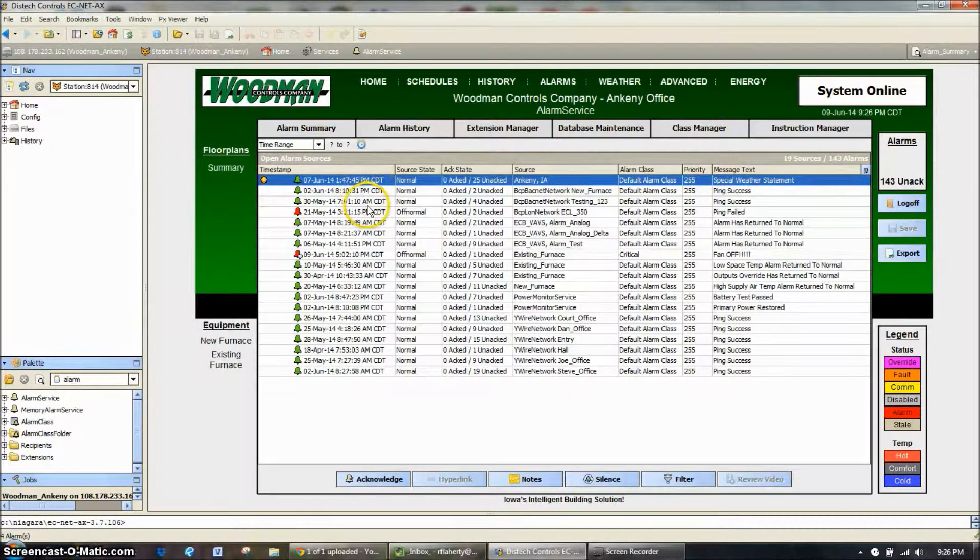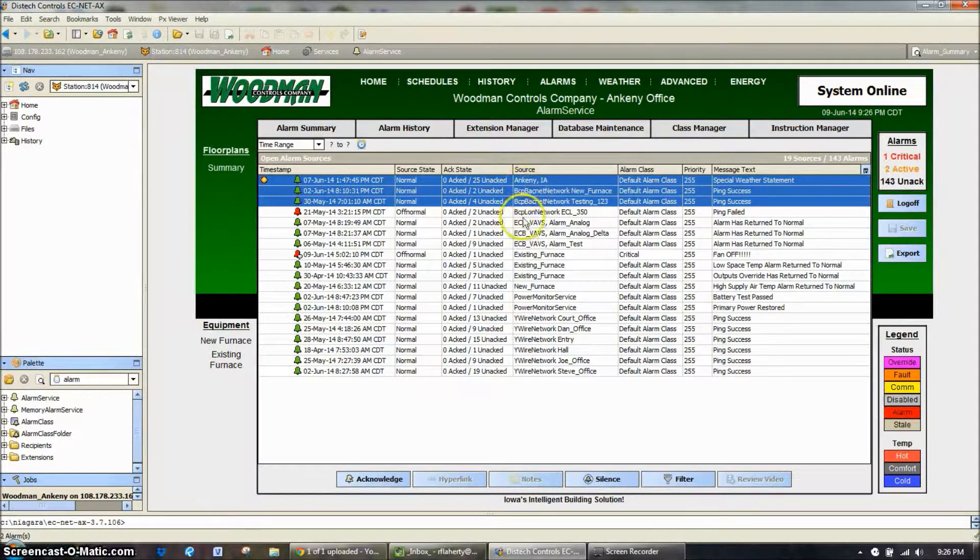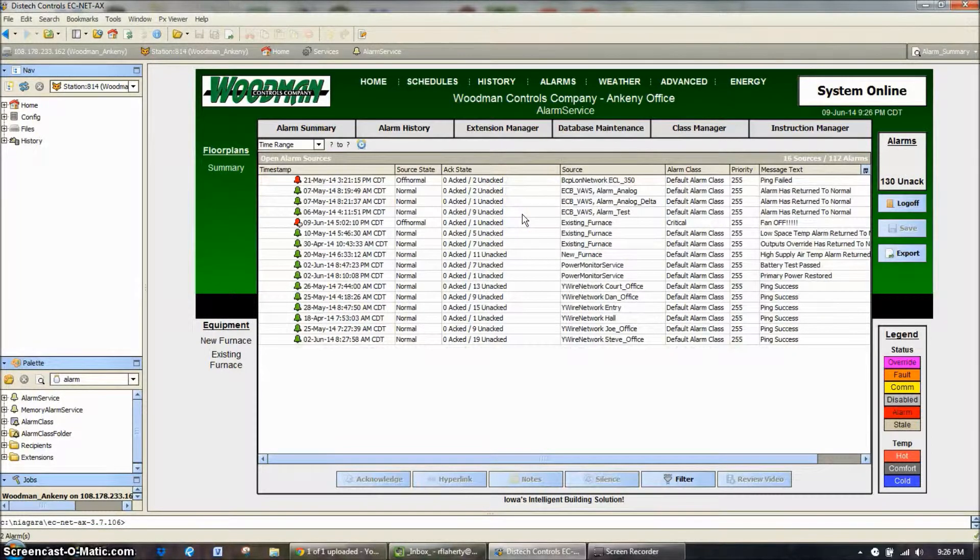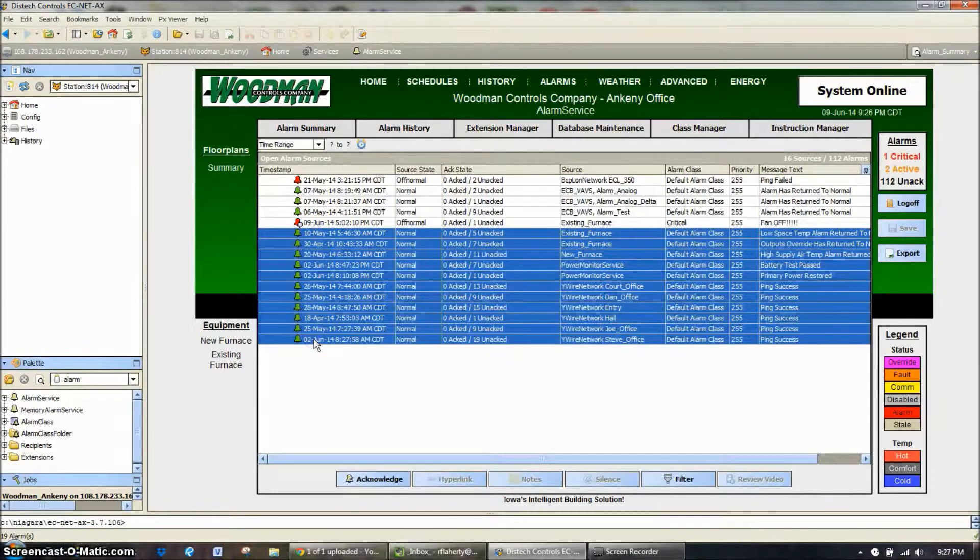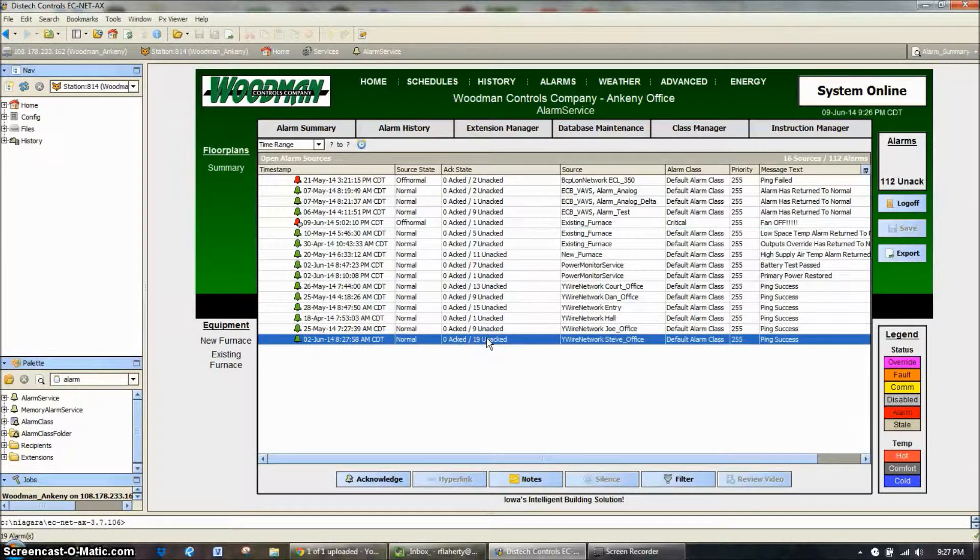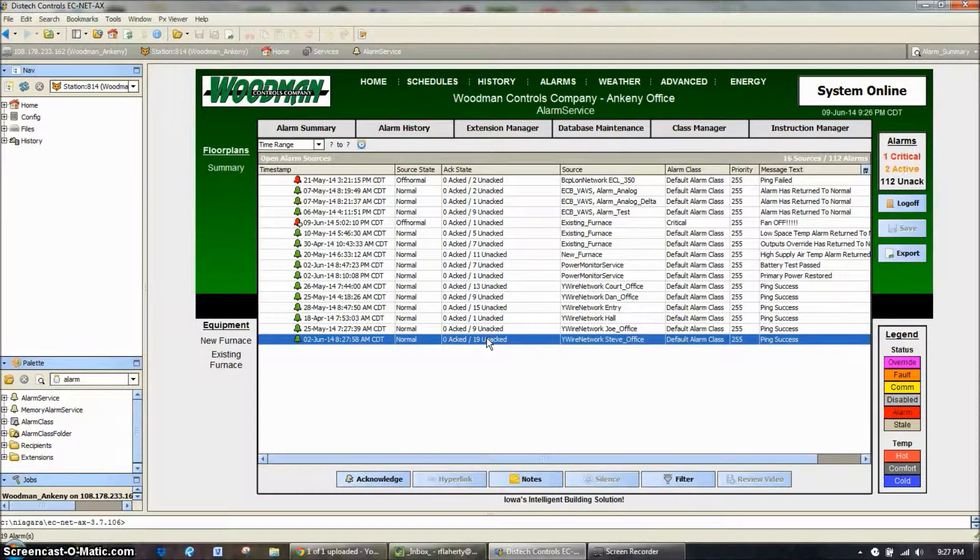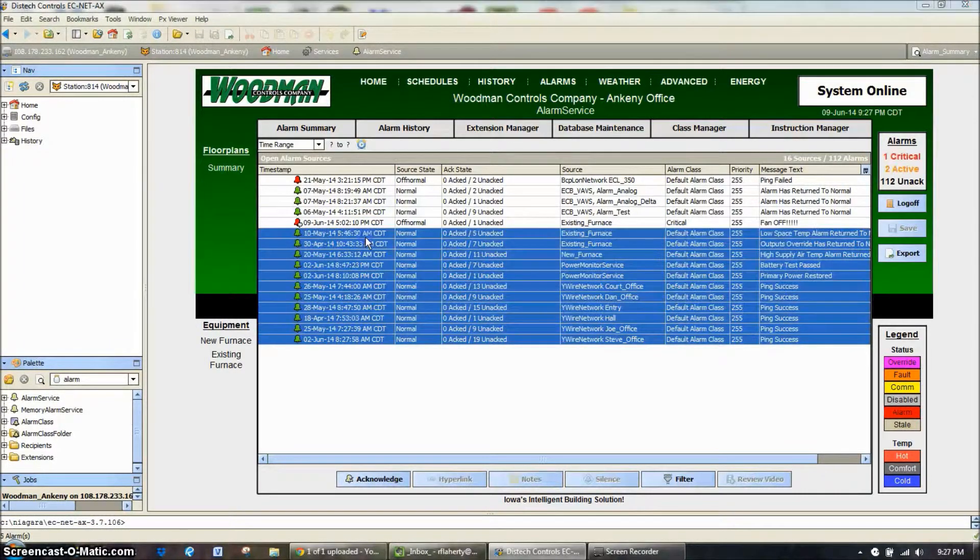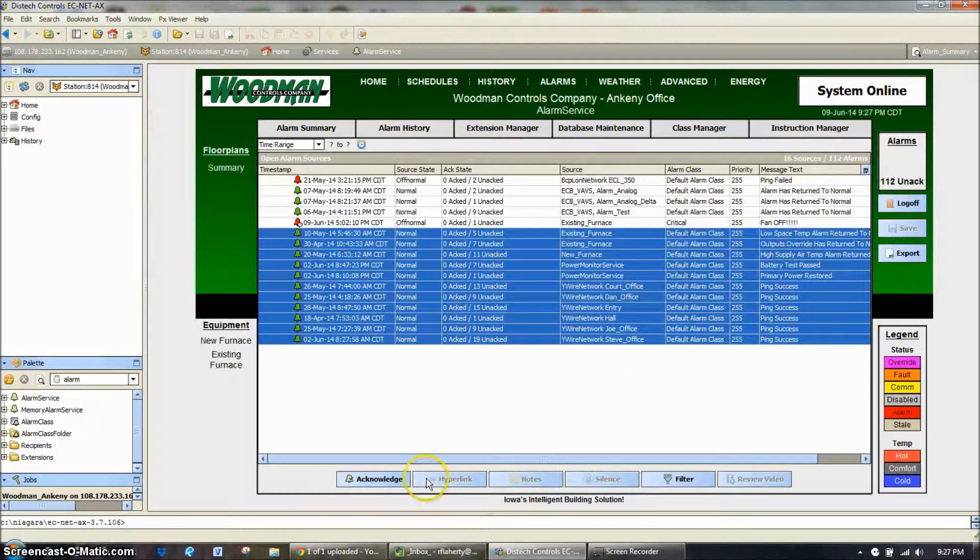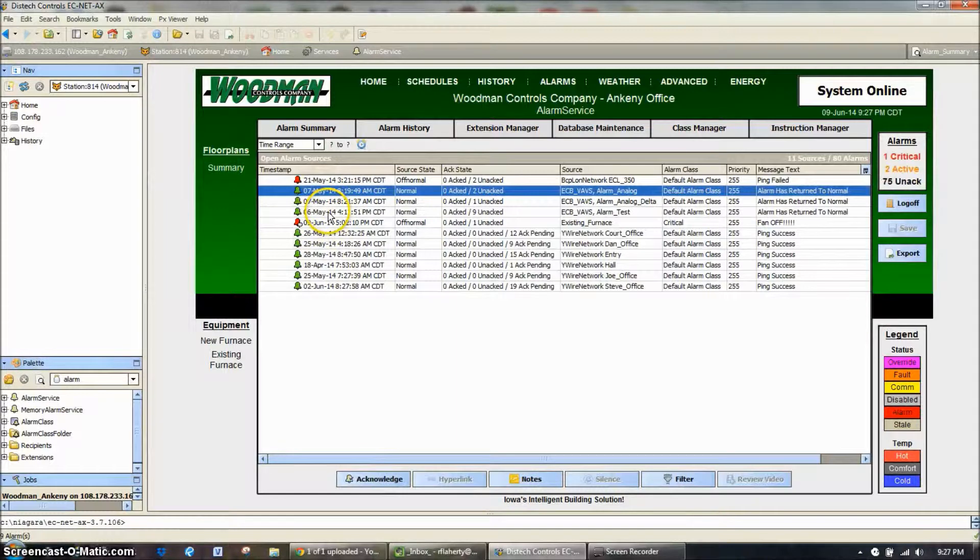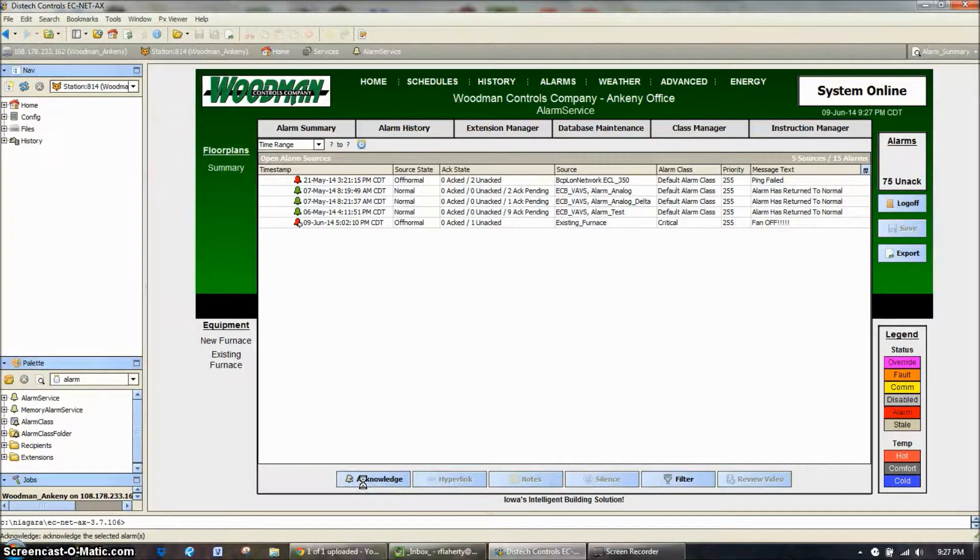So what I would do, daily, is if they are unimportant alarms, or things that have just happened and you know why, I would highlight them and acknowledge, and you'll see the acknowledge pending will be working in the background, and it'll acknowledge these alarms, takes a few seconds. So we're going to acknowledge all of these. Now, for example, down here, I know some of these as we've been testing with our system, we've been knocking controllers on and offline within the office. So we have a bunch of unacknowledged alarms that they've gone on and offline. That is normal. I know what they are. I don't really need to make a note because it's not really that important to me. So I'll hit acknowledge on those. These I know are just offline controllers we were testing. I'll acknowledge those.